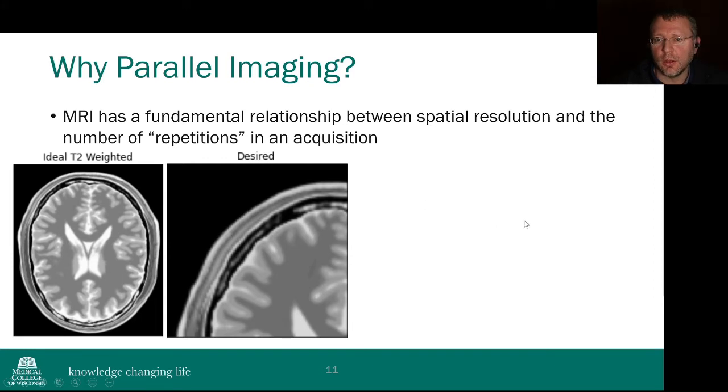Well, if you end up doing that, you'll run into the issue of Fourier encoding. And through the math that we use for encoding these images, we're actually not encoding the image itself, but the Fourier transform of the image itself. And when you do that, you're making an assumption that the image is periodic. In other words, when you see this image here, mathematically you're assuming that this image is here, and then if you were to extrapolate it out, there'd be another copy of the image up here, another copy down here, and in fact another to the left and to the right, in some sort of infinite grid of repeating images.